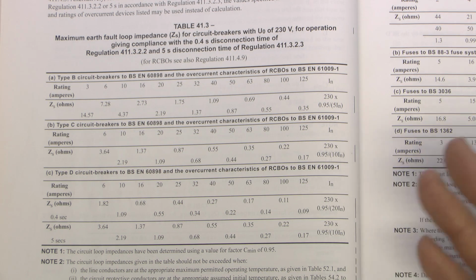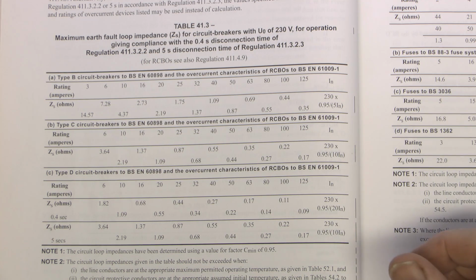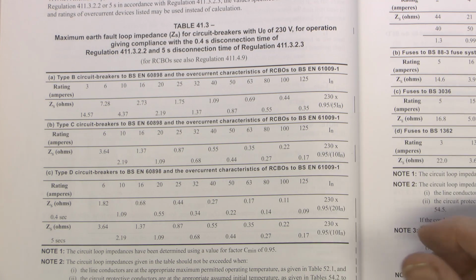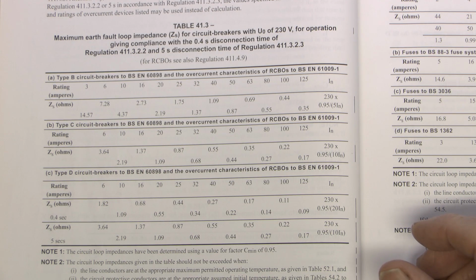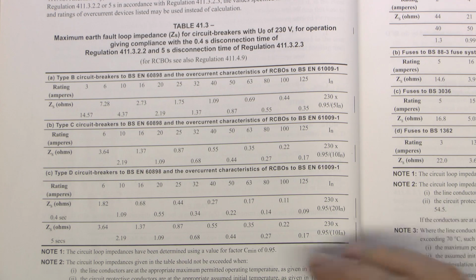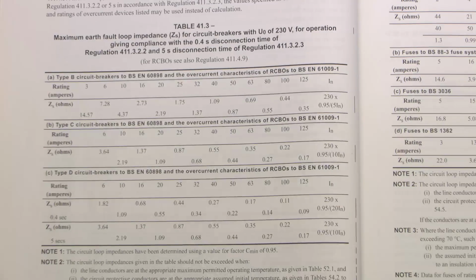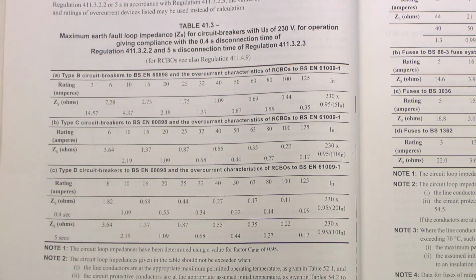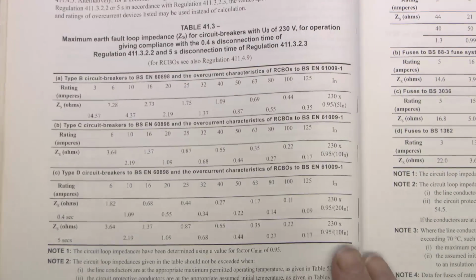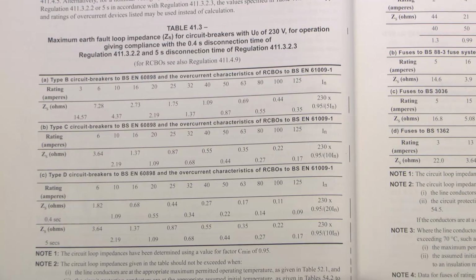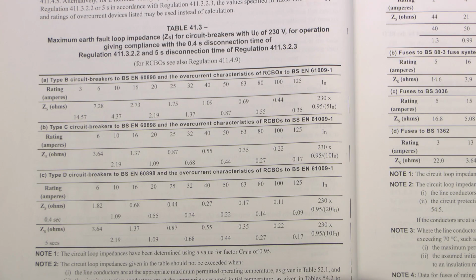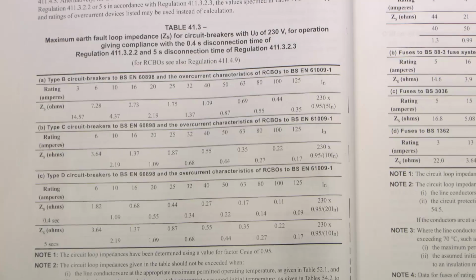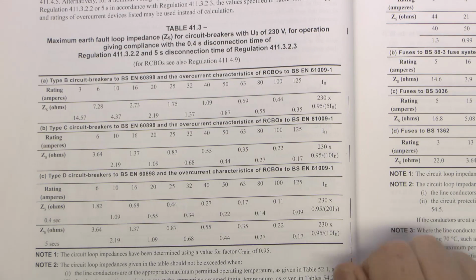So before changing the circuit breaker type, or in fact installing the first one in the first place, you do need to check the impedance of the circuit and confirm that it is actually within the requirements for the particular thing that you're using. And there's a table here, in fact there's several of them for different purposes in the regulations. Again, this is the yellow edition here, and this gives you some examples of the maximum earth fault loop impedance for various types of circuit breakers.